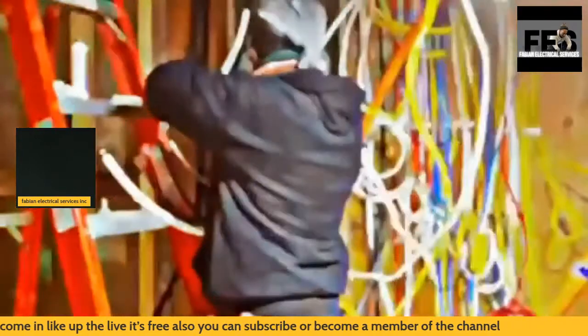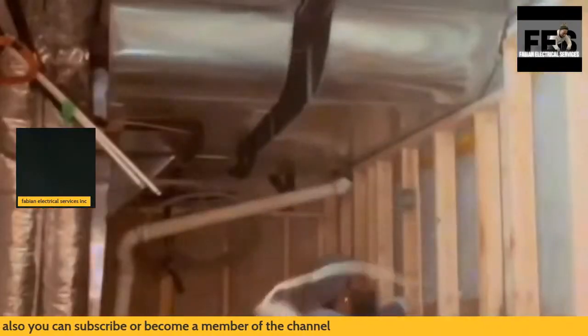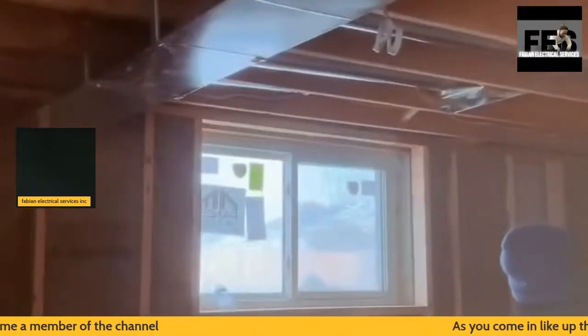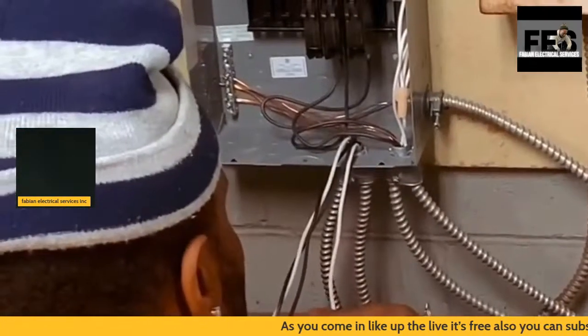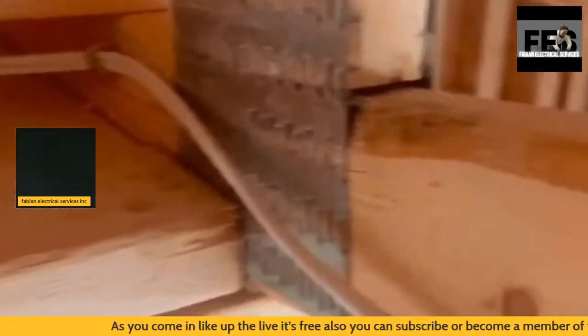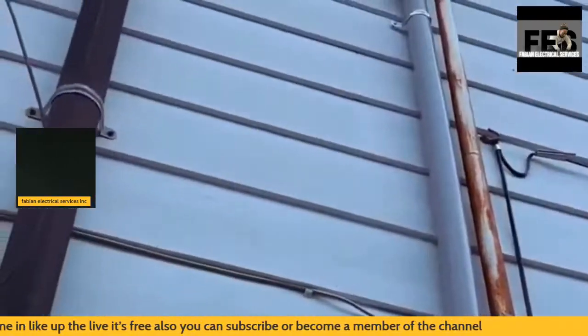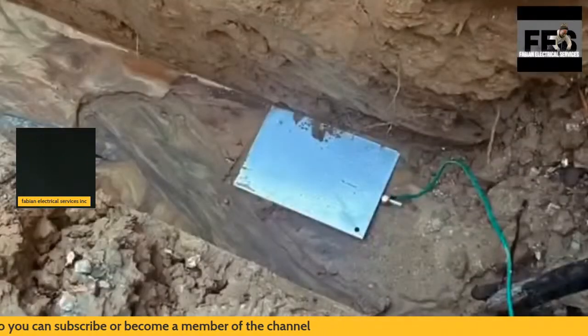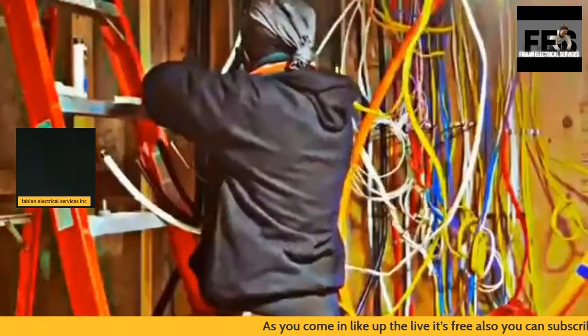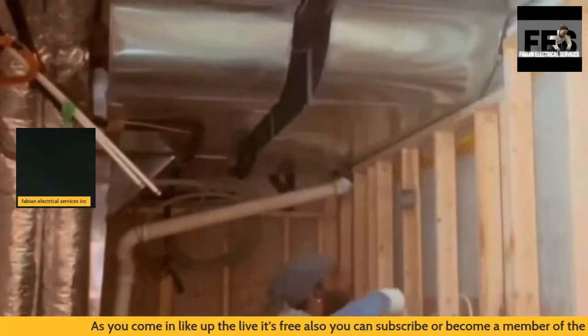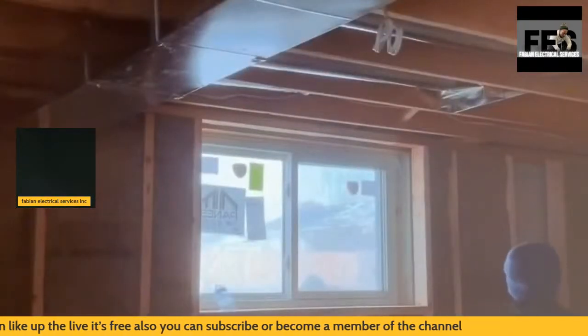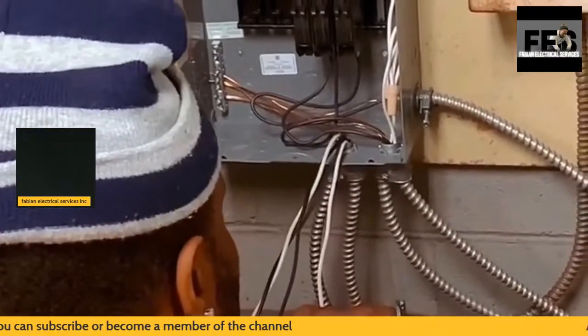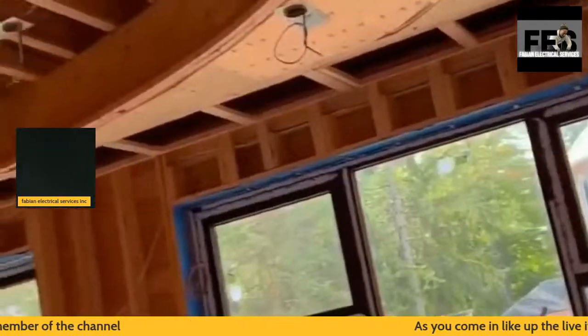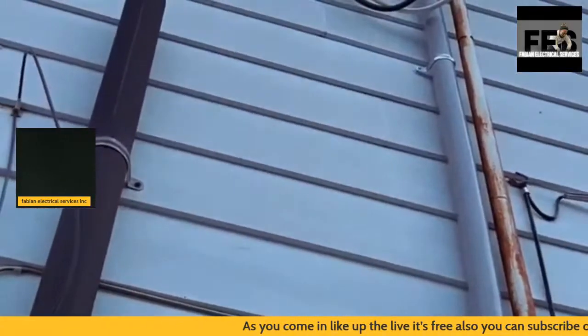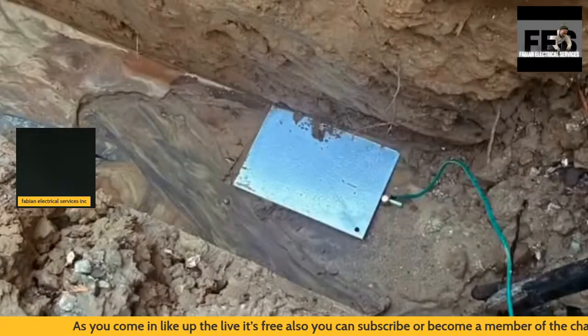A lot of it will be on 400 amp panels and 200 amp panels. There'll also be some troubleshooting where you'll get to see how I go about testing in the real world, whether it be a plug-in tester, a multimeter tester, or sometimes the regular tester. I prefer not to use that one a lot of times because it's not a guarantee of on or off. Those testers I try to use only when I'm in a quick jam. They're not really the go-to electrical tester you'd use if you're troubleshooting.